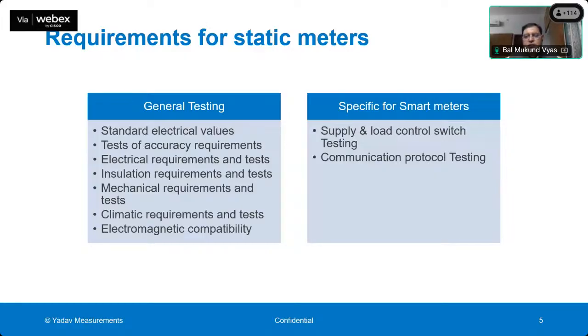Specifically for smart meters, the supply and load control switch testing is very, very important, because the switch, as I told you, is used for connect and disconnect, but it has to be a very rugged switch. It should not fail, otherwise the supply to the consumer will be disconnected, or it will be connected permanently. So both are not good.